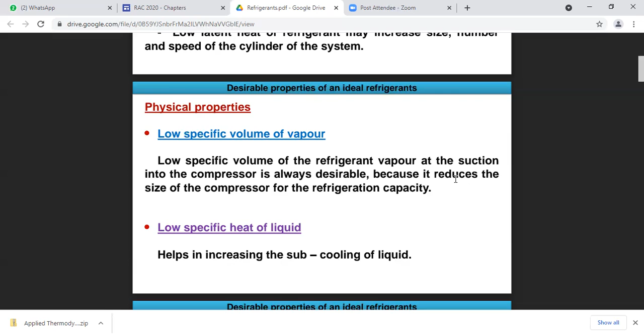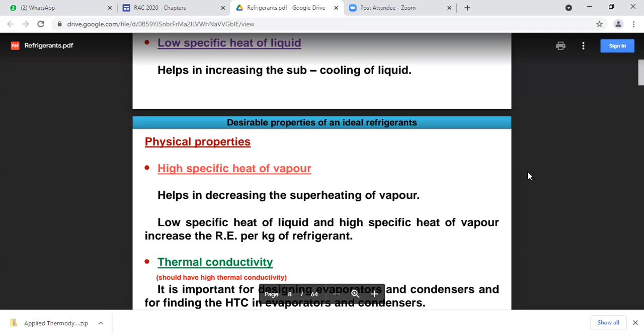Next, the second point is low specific heat of liquid. It helps in increasing the subcooling of the liquid. Next, high specific heat of vapor. In the case of high specific heat of vapor, we are finding that it helps in decreasing the superheating of vapor. So low specific heat of liquid and high specific heat of vapor increase the refrigerating effect per kg of the refrigerant. So these are the physical properties we have discussed.